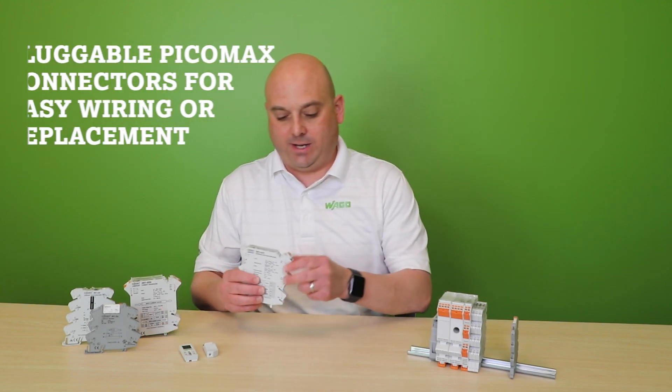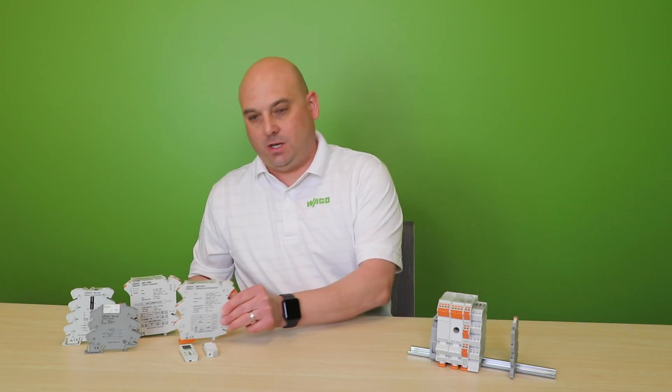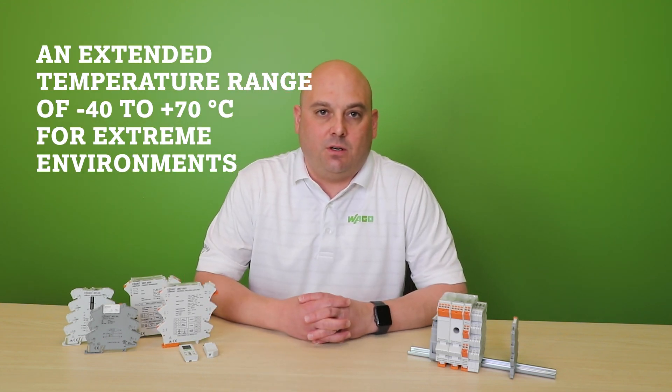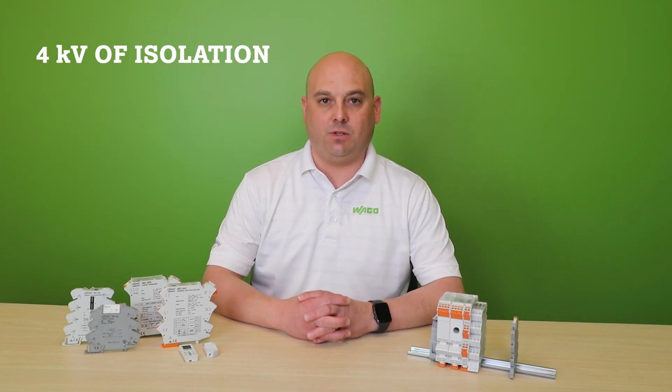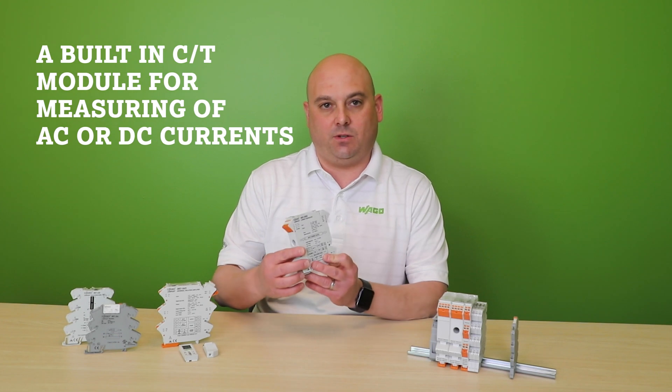These have pluggable PicoMax connectors for easy wiring and replacement, an extended temperature range of minus 40 to plus 70°C, up to 4 kV of isolation, and a built-in CT for measuring AC or DC currents.